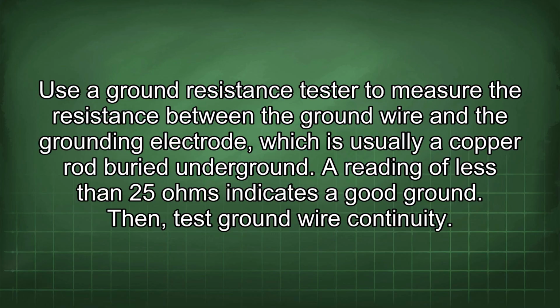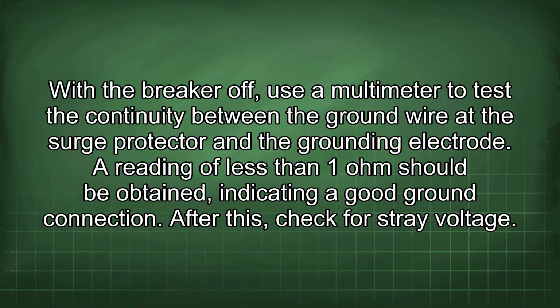Then test ground wire continuity. With the breaker off, use a multimeter to test the continuity between the ground wire at the surge protector and the grounding electrode. A reading of less than 1 ohm should be obtained, indicating a good ground connection.